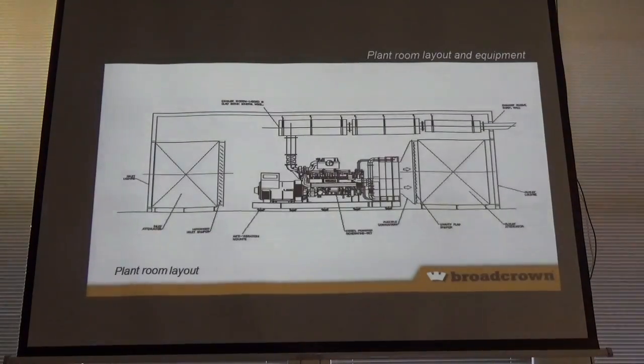You might have air coming in at the same end. Duct it to deliver the inlet air to the back of the room. But either way, from that point to that point, wherever it falls on the wall, or ideally the other side of the building, because if the inlet and the discharge are right next to each other, what's going to happen? It's going to draw the air in straight away. You're going to get recirculation problems, shutdown on overheat, depending on the circumstances and situation. But either way, it's certainly not going to run properly to its design.